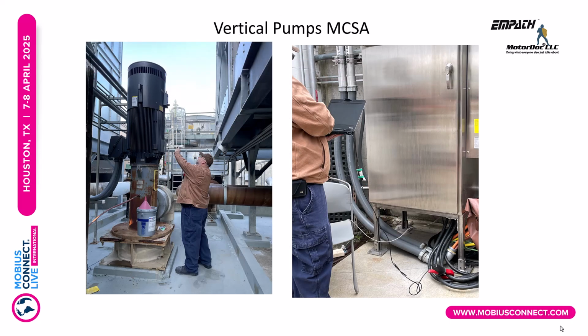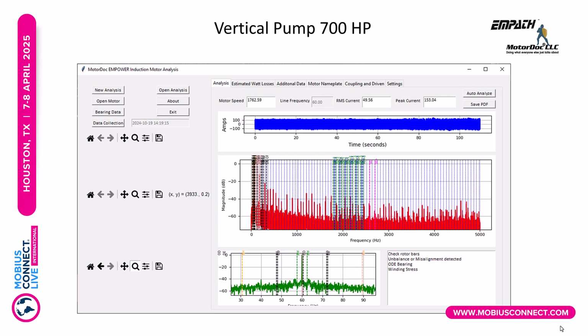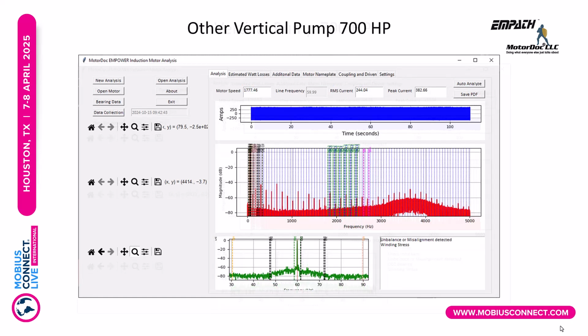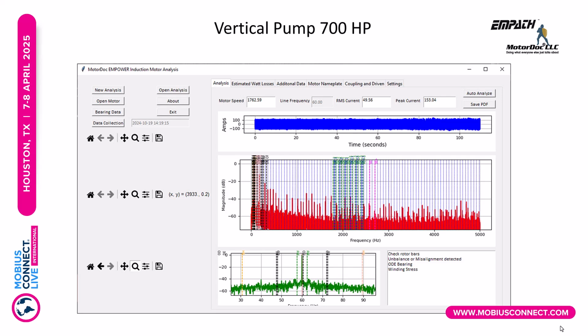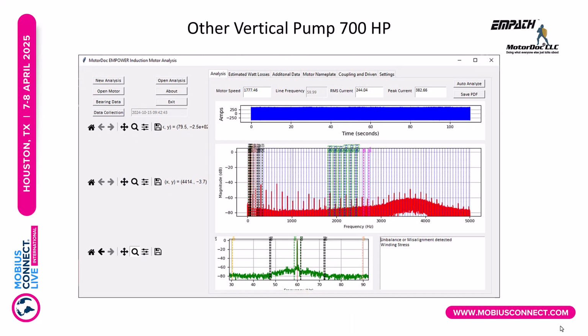Let's take a look at a 700 horsepower vertical. Yeah, that's me in the field, and we're taking data there. So in this case with current signature analysis, we can see that it's calling out different conditions. Again, compared to another one, you'll notice just the way the shape is down there, it's actually operating at a higher frequency, I think about 8 kilohertz if I remember right. And this one has a little hump there, but the noise floor is a little low. That has to do with all the noise in ground and also the noise and harmonics in the system.